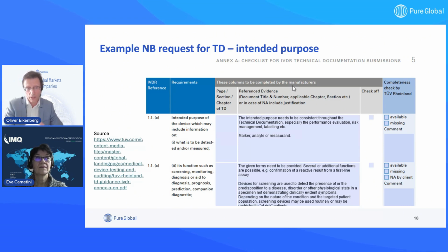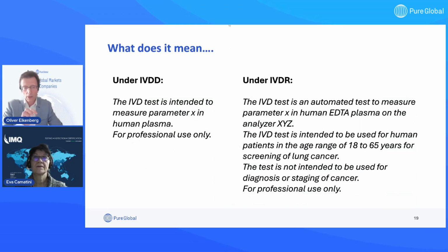What does it mean? For example, an IVDD intended purpose will change from a pure analytical definition, like measuring a specific parameter in human plasma, into a more defined intended purpose. This parameter is measured in human EDTA plasma on the analyzer, and so on. And then the IVD test is intended to be used for human patients in the age range of, say, 18 to 65 years, for screening of lung cancer. So the test is not intended to be used for diagnosis or staging of cancer. Here, this is maybe an adequate intended purpose, just as an example, and it includes the indication, the target population, and the specific scope and claims of this test.